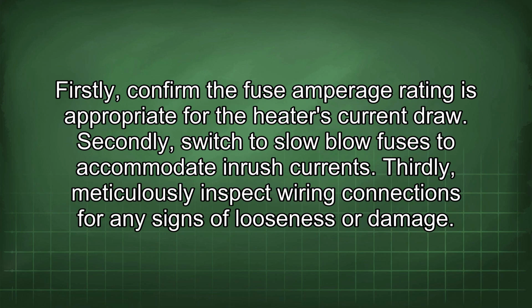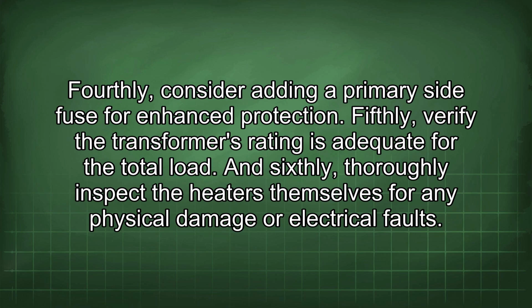Firstly, confirm the fuse amperage rating is appropriate for the heater's current draw. Secondly, switch to slow blow fuses to accommodate inrush currents. Thirdly, meticulously inspect wiring connections for any signs of looseness or damage. Fourthly, consider adding a primary side fuse for enhanced protection. Fifthly, verify the transformer's rating is adequate for the total load. And sixthly, thoroughly inspect the heaters themselves for any physical damage or electrical faults.